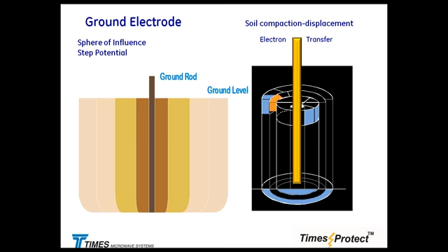Okay, so as you see, we started coming down from the top of the tower. We furnished grounding jumpers. In this example, one is right below the antenna. Another one is going to be when we transition RF feeder from the vertical to the horizontal. There is the cable tray. One thing before I forget, if you are grounding cable tray directly to the tower, okay, if you are bonding the end of the cable tray directly to the tower, please do not bond it to the master ground bar on the outside of the shelter or cabinet.